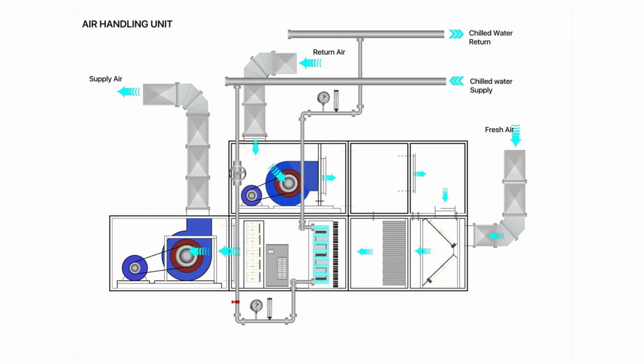Let's study the operation of the AHU in more detail. Knowing the system's flow will help you decide where to place a sensor or device. So the unit takes air from the outside and then filters it in this area, the pre-filter or aluminum filter and bag filter compartment. Dust and debris from the air are captured by air filters. After filtering, the air will be reconditioned by the cooling coil or heating coil. The supply fan will then take the clean air and direct it into the room or space. And from the room, the air returns to the AHU, and the return fan will take it inside the unit and mix it with fresh air. So that was the AHU functioning cycle.